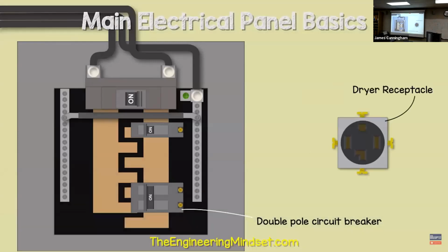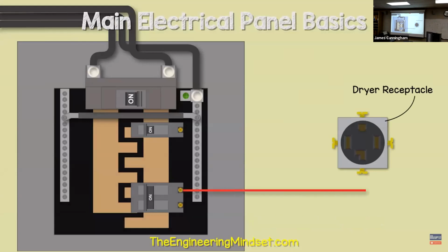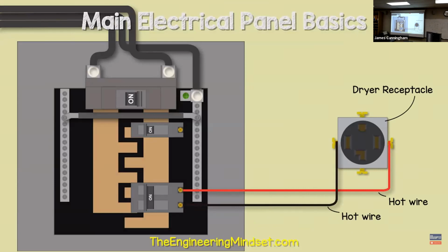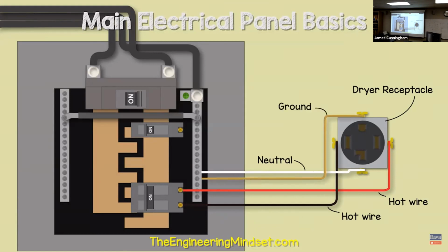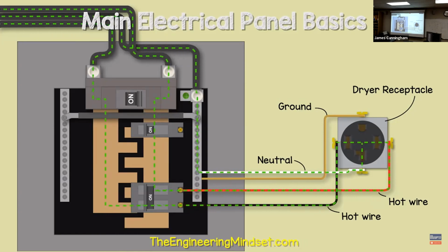If we look at the dryer circuit example, we run the red hot wire from the circuit breaker, which is connected to the main bus bar number 2, and we run this to the receptacle. Then we run our black hot wire from the other terminal of the circuit breaker, which is connected to bus bar 1, and we connect that to the receptacle also. In this case, we have the neutral wire connected between the neutral bus bar and the receptacle, which will allow us to get either 120 or 240 volts from the output. Then we have a ground wire to provide a safe route for any fault current. Now we can either connect across the 2 hot wires for our 240 volt connection, or between the hot wire and the neutral wire to get 120 volt connection.